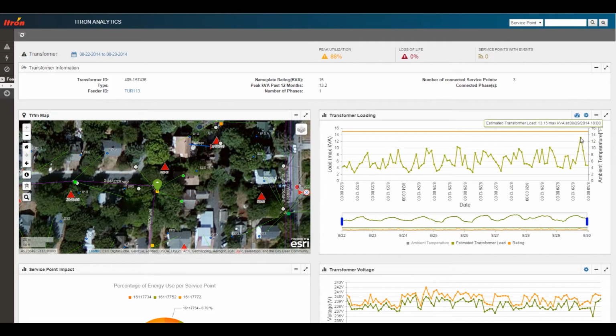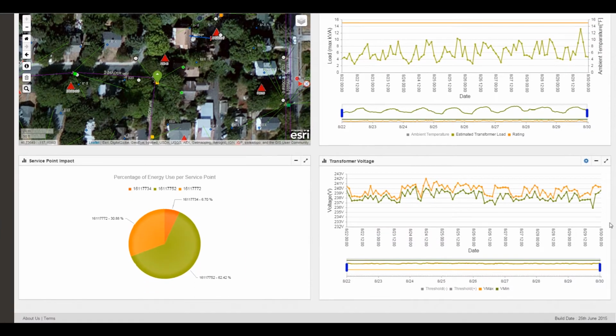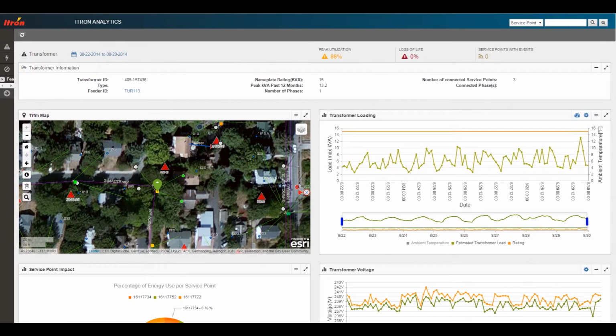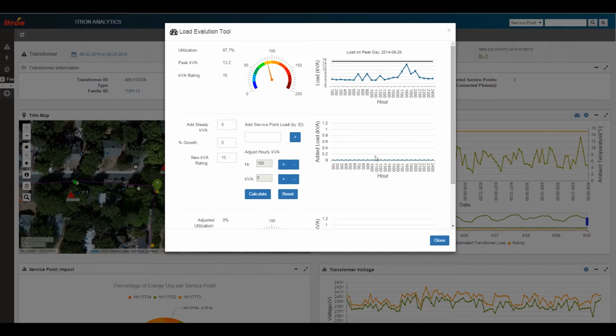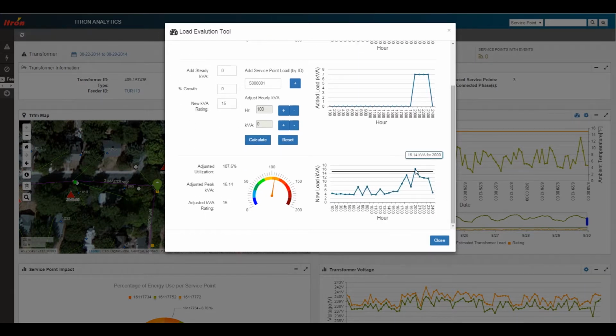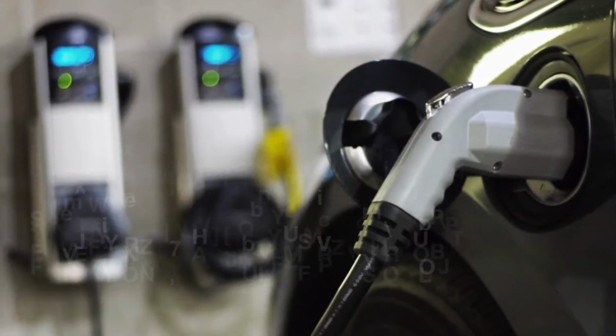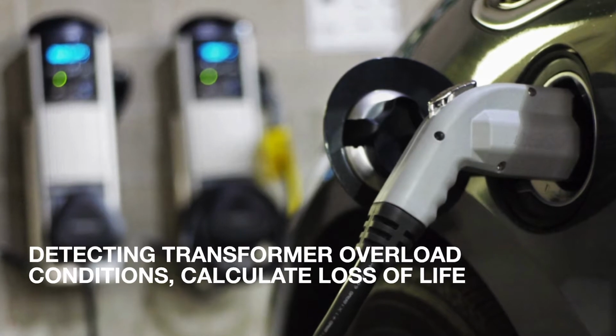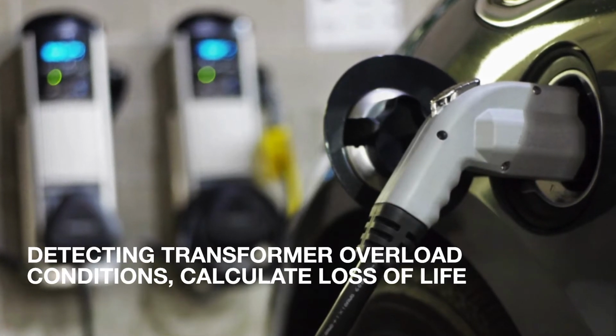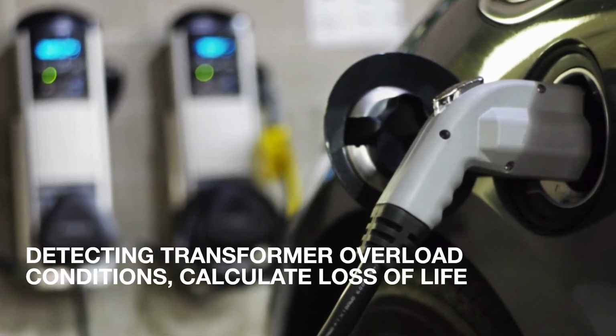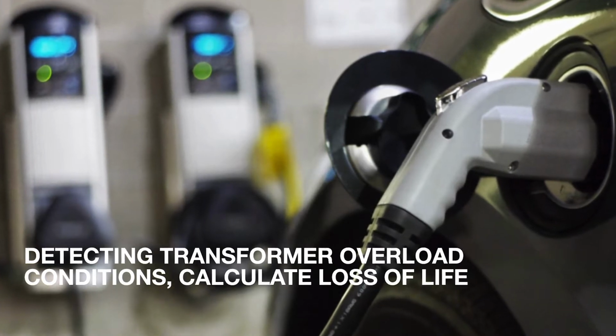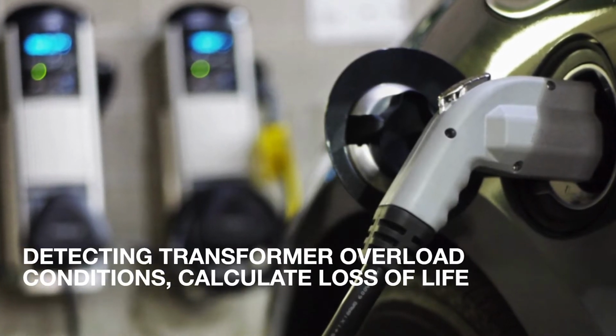After a review of the location in question, the planner navigates to the transformer serving the customer. The planner then uses the load evaluation tool to evaluate the impact of an additional fixed load or hourly load profile to the transformer. In this scenario, the load addition will exceed transformer rating, and the asset would likely need to be replaced. In the next scenario, the application continually monitors transformer loading across the system and alerts planners to overloads and excessive loss of life conditions caused by addition of electric vehicles and other unreported load increases.